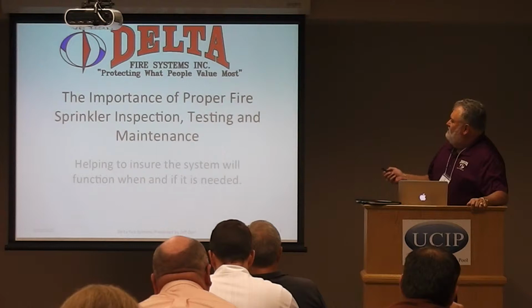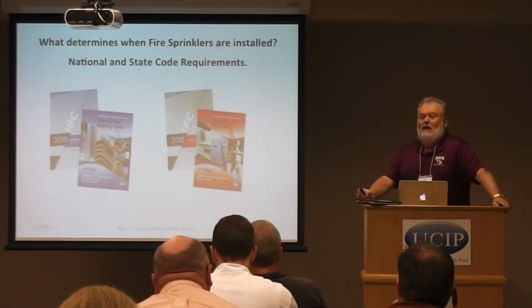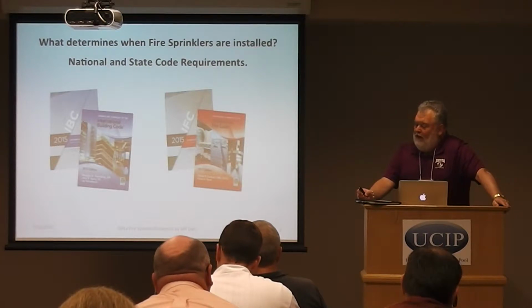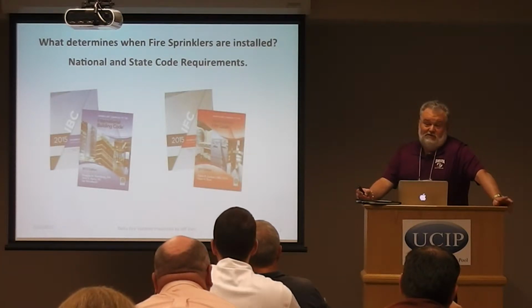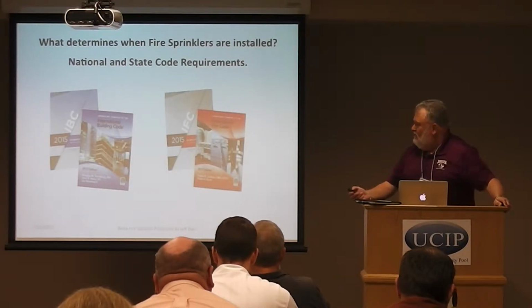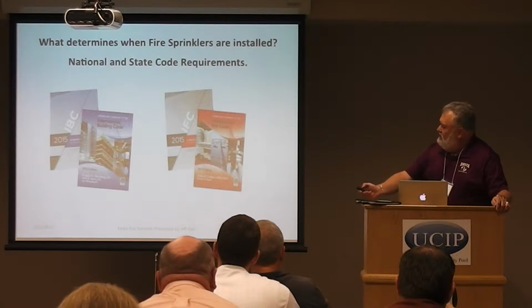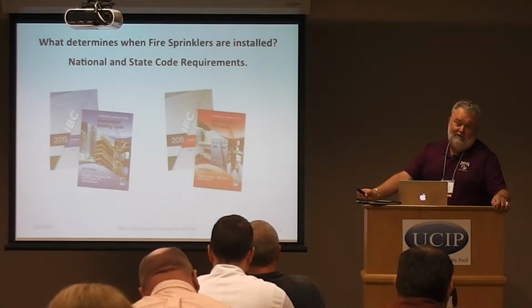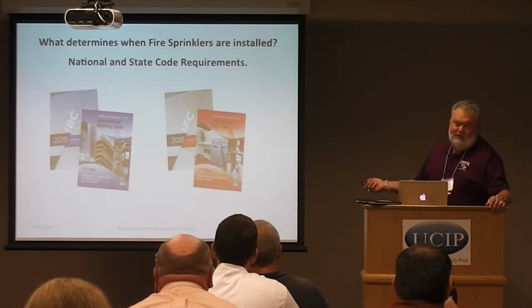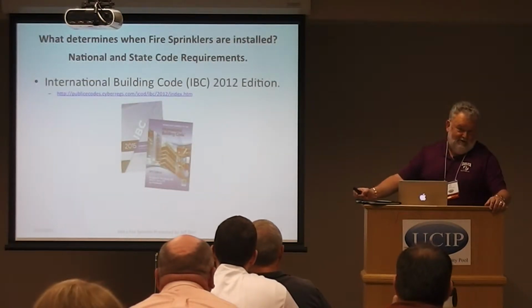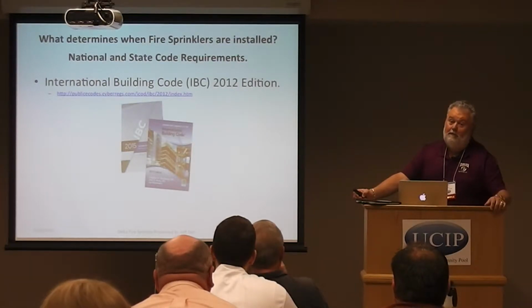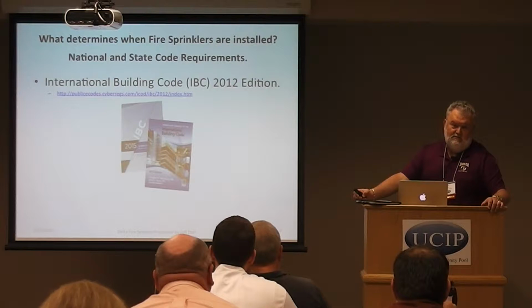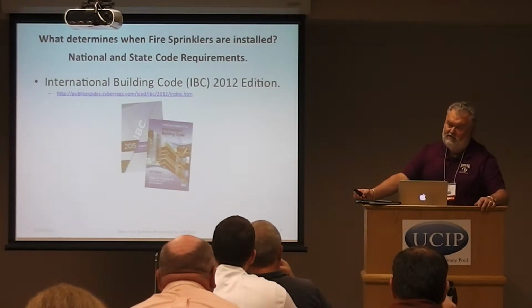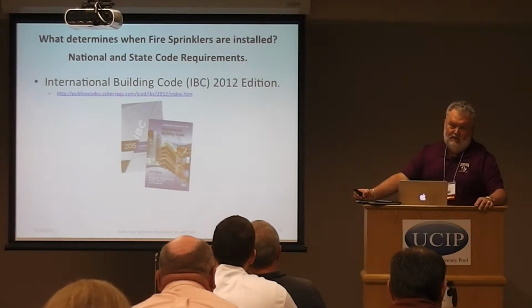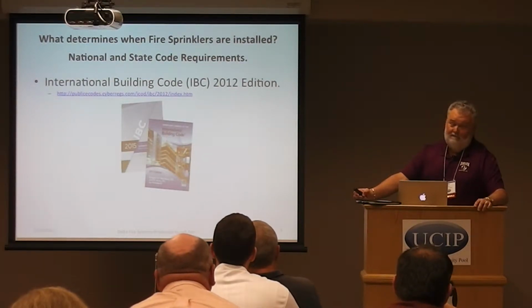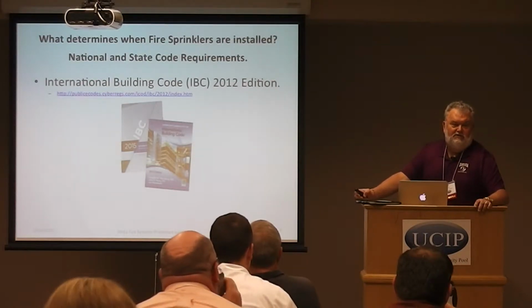Now, it's often said, you've got a sprinkler system. Why do we have that sprinkler system in? And it's really quite easy. There are national codes and state codes that dictate when sprinklers are going to be installed in buildings. As you see, this is the 2015 International Building Code and Fire Code. Unfortunately, the state right now is on the 2012 code, and we're in the process, and I sit on a code analysis council, of reviewing the changes between the 2015 and 2012. So there may be some changes coming up, but be aware that we're on the 2012 code.